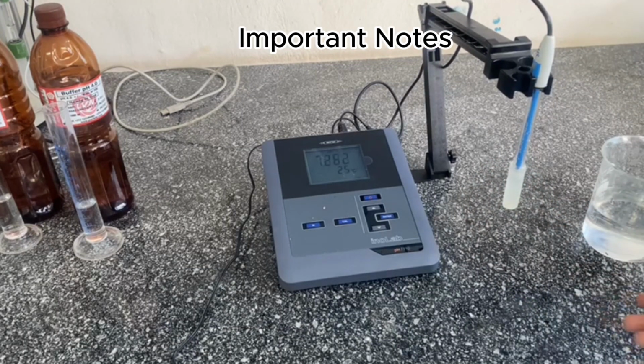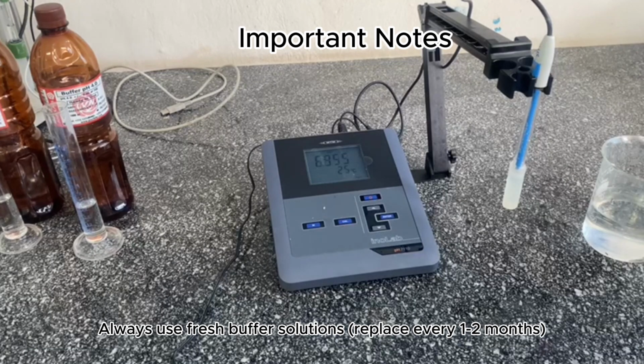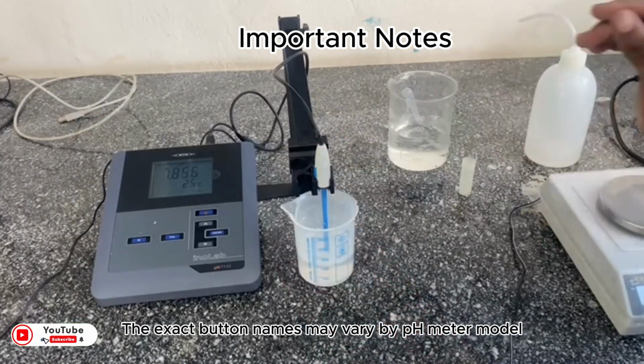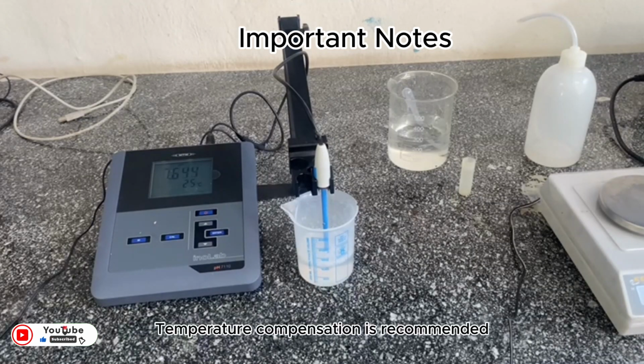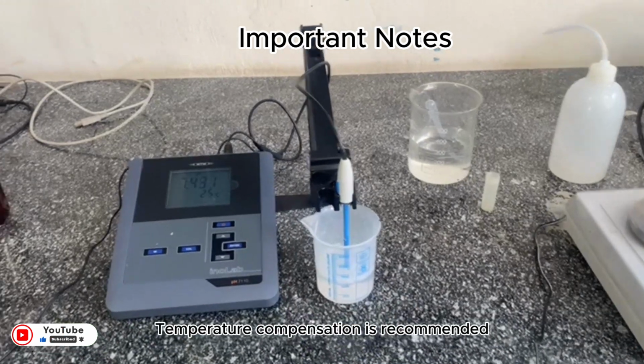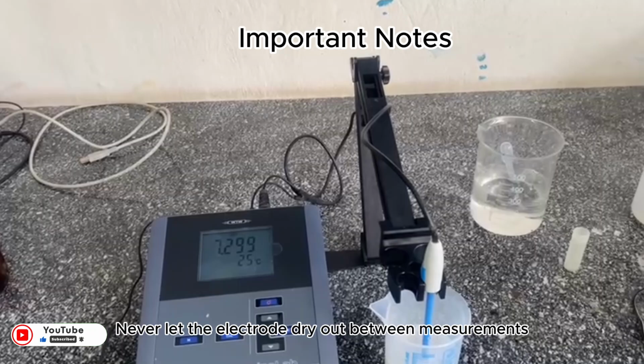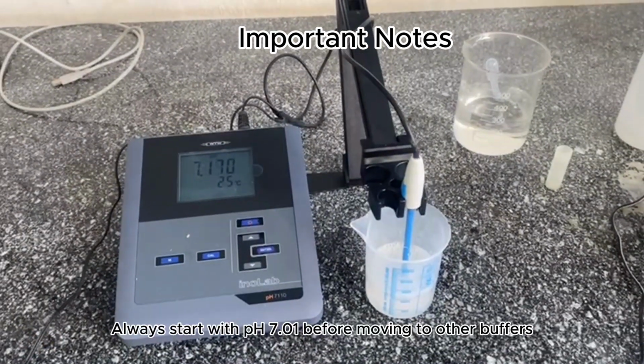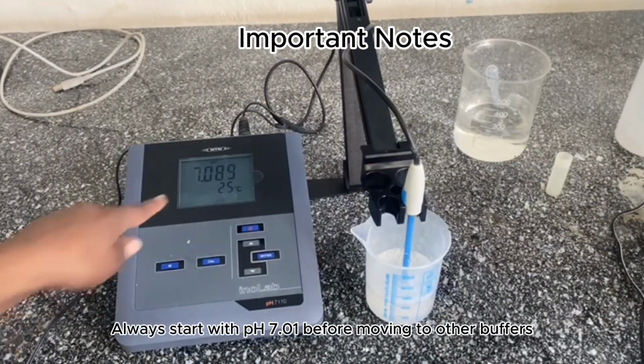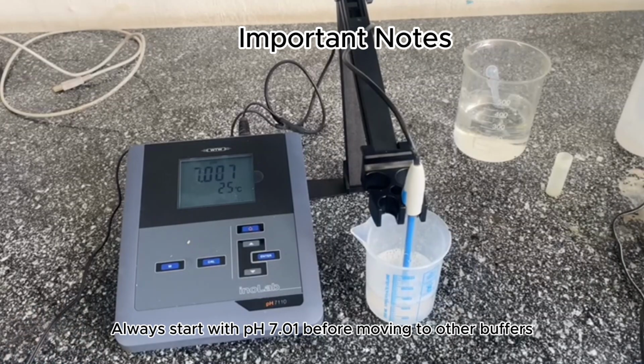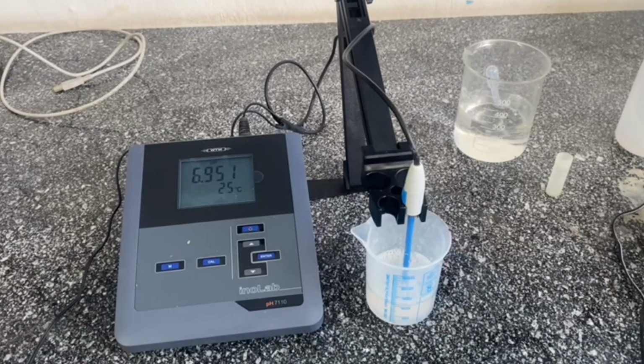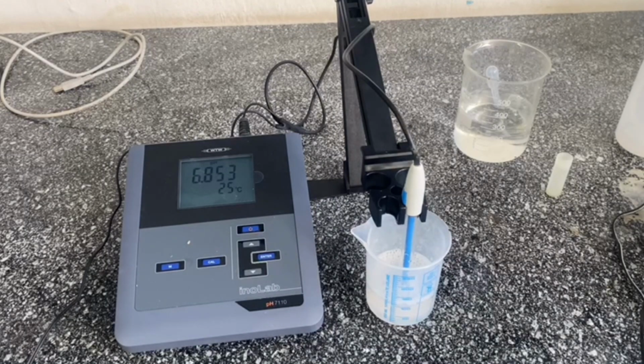Important notes. Always use fresh buffer solutions. Replace every 1 to 2 months. The exact button names may vary by pH meter model. Temperature compensation is recommended. Never let the electrode dry out between measurements. Always start with pH 7.01 before moving to other buffers. This corrected procedure ensures accurate calibration following standard laboratory practices. The sequence, 7-4-10, is important for proper electrode conditioning.